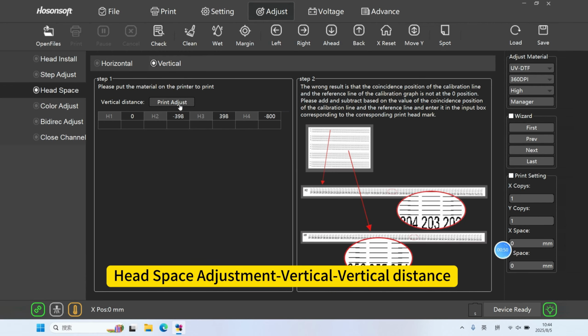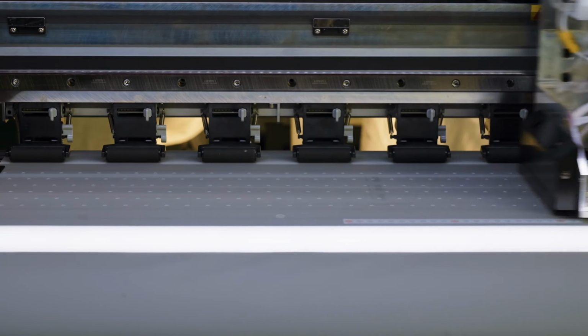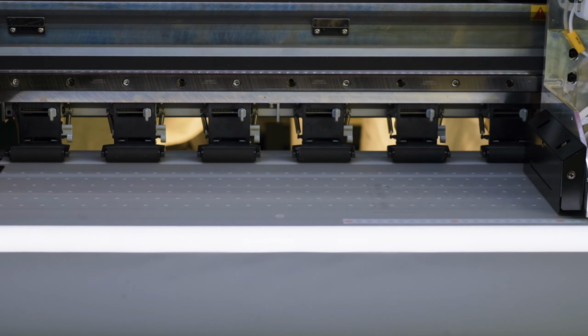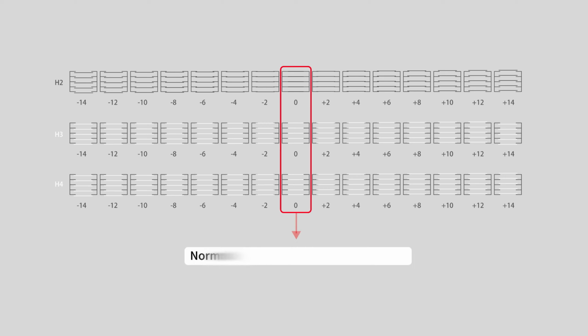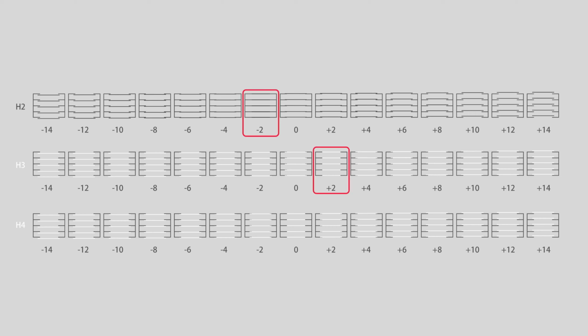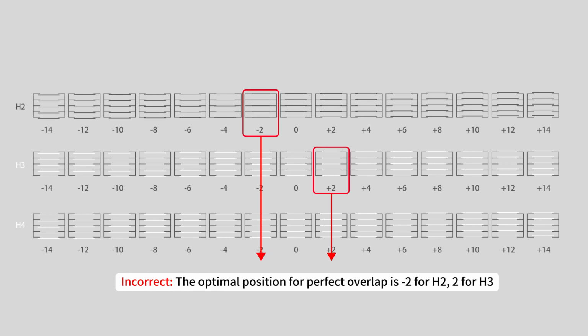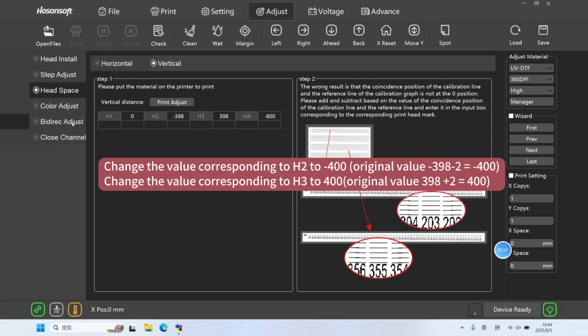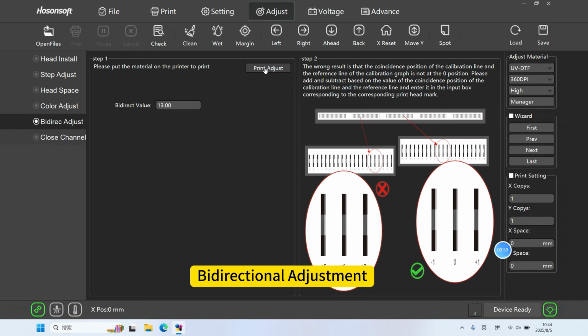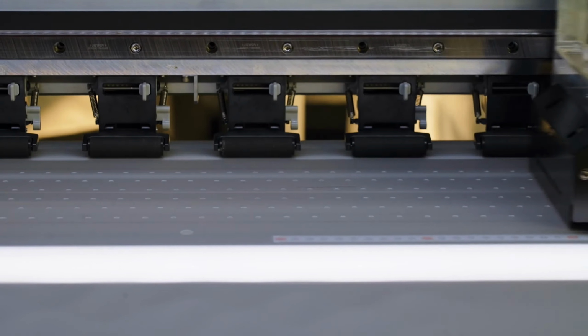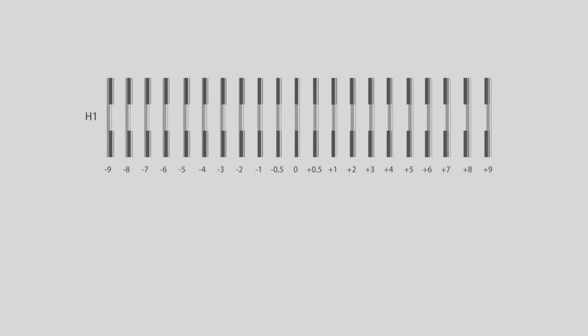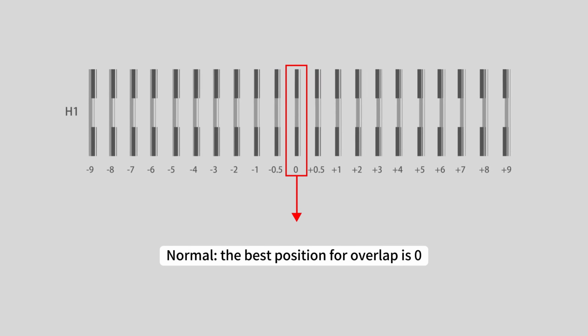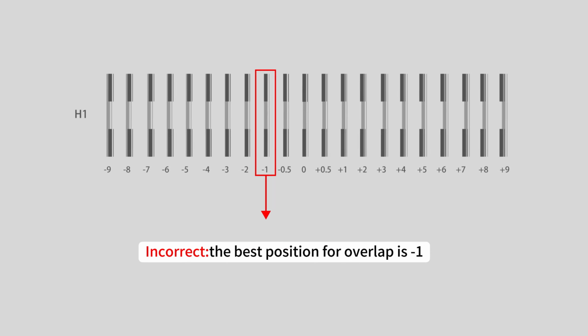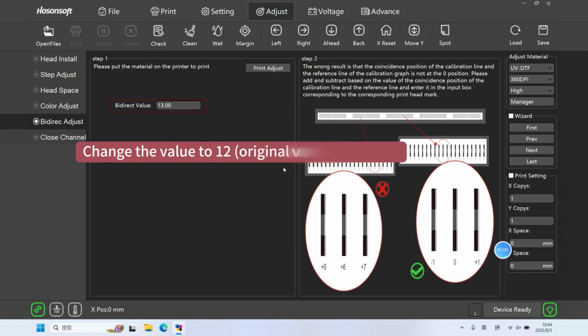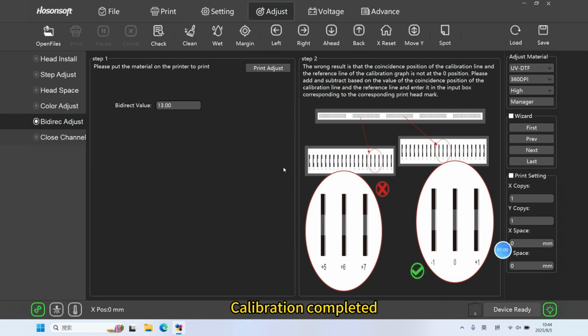Headspace adjustment vertical distance. Normal: the best position for overlap is 0. Incorrect. Bidirectional adjustment. Normal: the best position for overlap is 0. Incorrect: the best position for overlap is -1. Change the value to 13. Calibration completed.